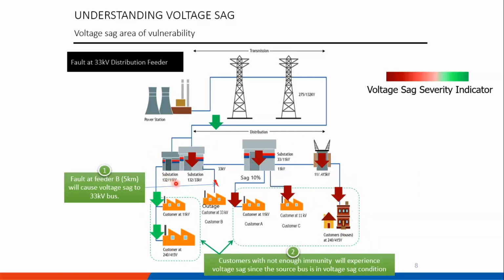The 132 kV connected customer here may have some effect, but it's not as bad as the customer connected to this bus bar. And the transmission connected is still in the green zone. So from this diagram we can say that the voltage sag severity depends on the fault. The closer the fault to the source, the higher the fault level, and the more severe the voltage sag.